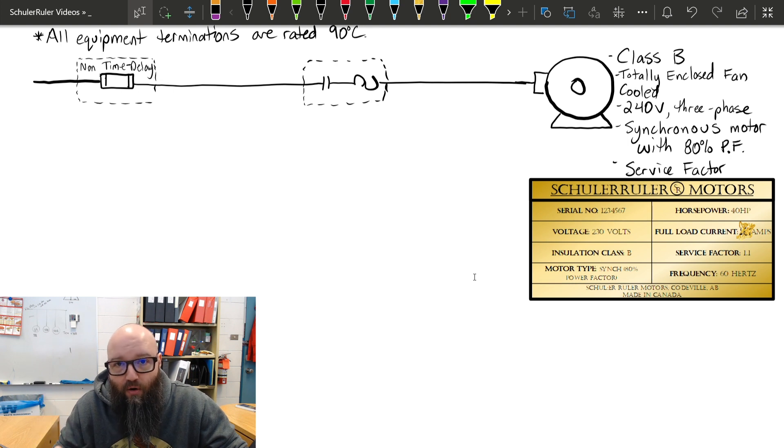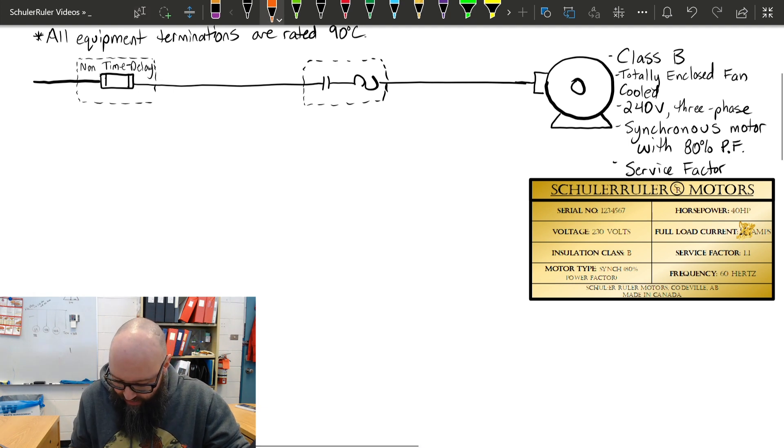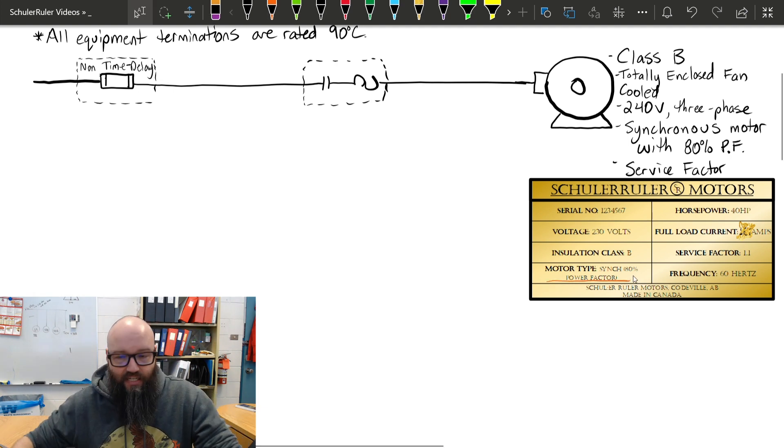If this was a synchronous motor with a unity power factor, we could just take our horsepower and our rated voltage, our nominal voltage with the corresponding column, and we could just pick an FLA based straight off of that. But if you look at the nameplate value here, our nameplate states that this is a synchronous motor with an 80% power factor.